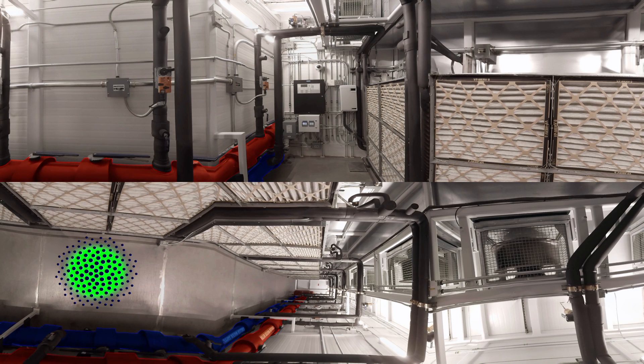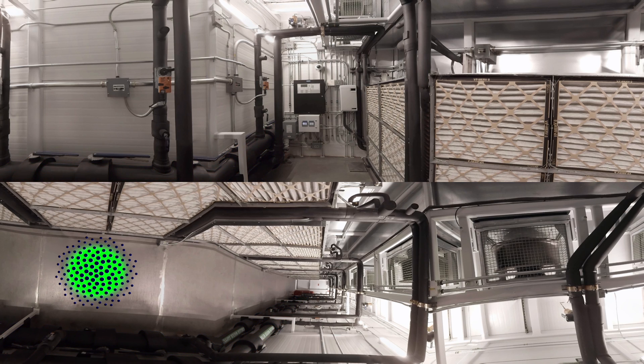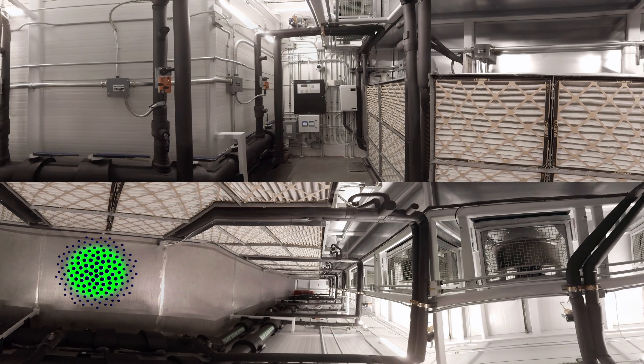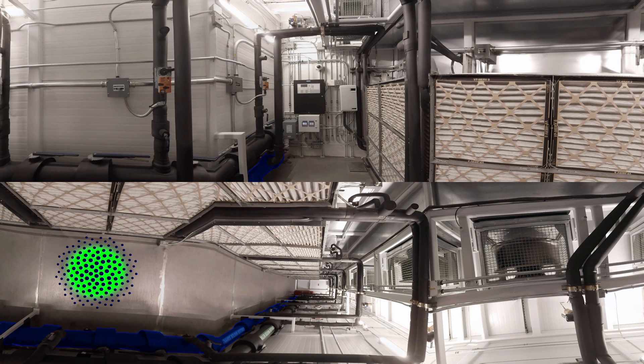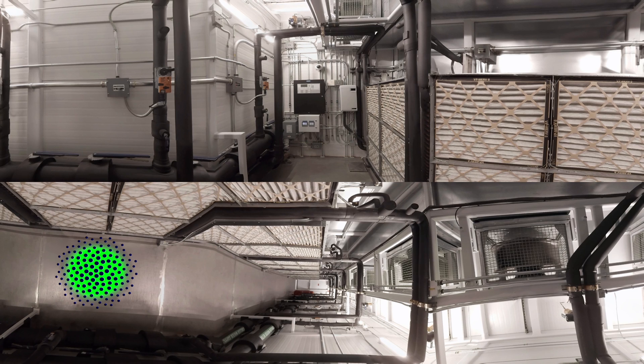On one side of the unit, you'll see two pipes, the return and supply water loops. Because this unit operates in a closed chill water loop, the return temperature is set to 55 degrees Fahrenheit, while the supply temperature is set to 45 degrees. All key set points are adjustable by the operator.